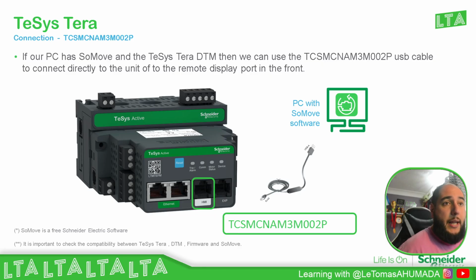So in order to connect to the TeSys Tera, what we need is this extension cable, okay, that basically has a RJ45 on one side and the other one the USB-A. This is the reference, which is the same that we use to program the drives or the TeSys T. Then what we need is to have SoMove already installed on the PC and the DTM for the TeSys Tera. Then we have two ways to connect to the TeSys Tera using this cable.